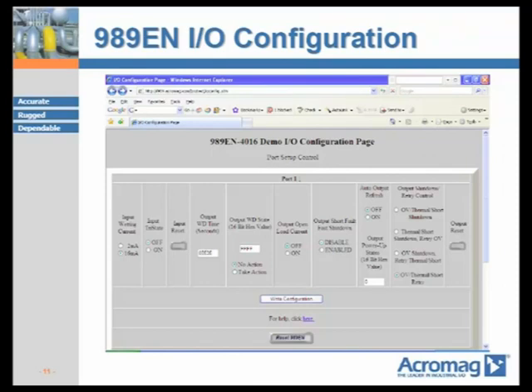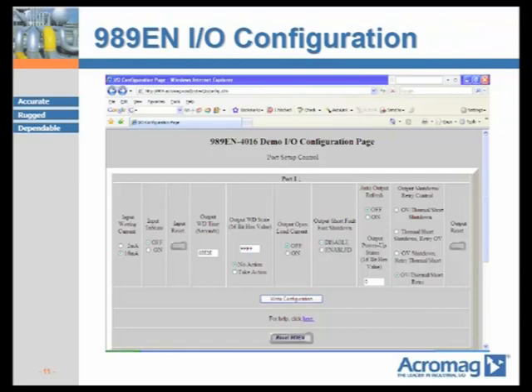This page shows the flexible configuration settings for the 16-channel discrete I/O device. In the first column, wetting current sources can be set to 2 milliamps or 16 milliamps. At 16 milliamps, the inputs send 16 milliamps into the dry contacts for 20 milliseconds when a short is detected, then fold back to 2 milliamps continuously — ideal for extending the life of dry contacts subject to oxidation. When the input tri-state setting is on, the current sources are gated off and discrete inputs act as traditional high-impedance logic gates. Other notable settings include programmable watchdog timer and output states for fail-safe outputs, programmable power-up states, open load detection, short fault protection, and the ability to shut down or retry outputs in the event of an over-voltage or thermal short condition.